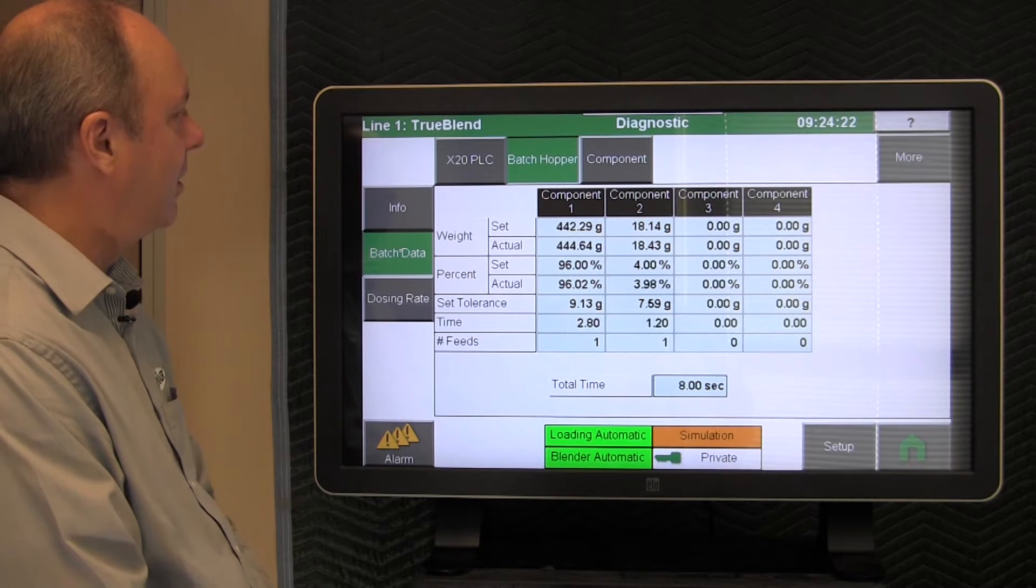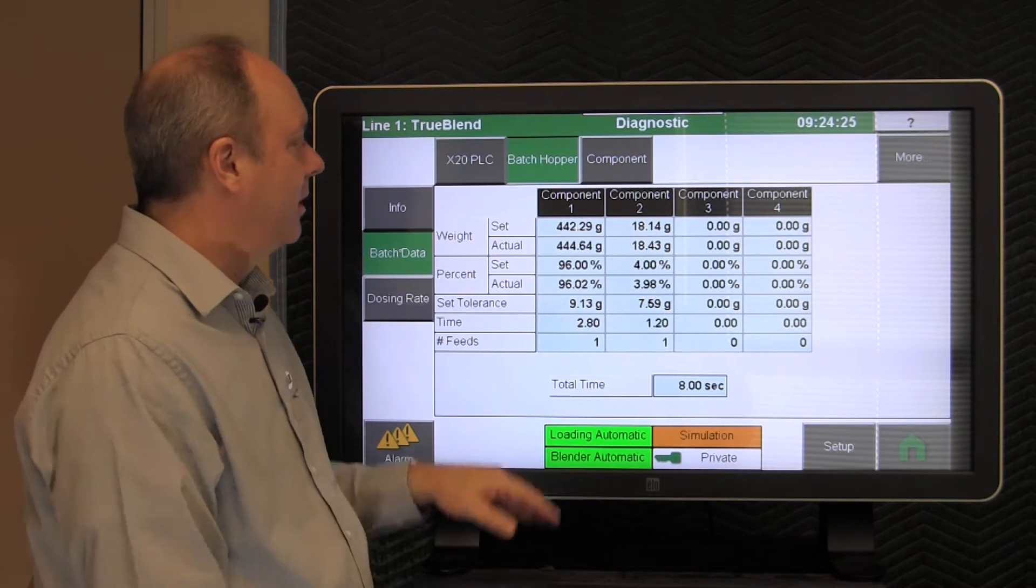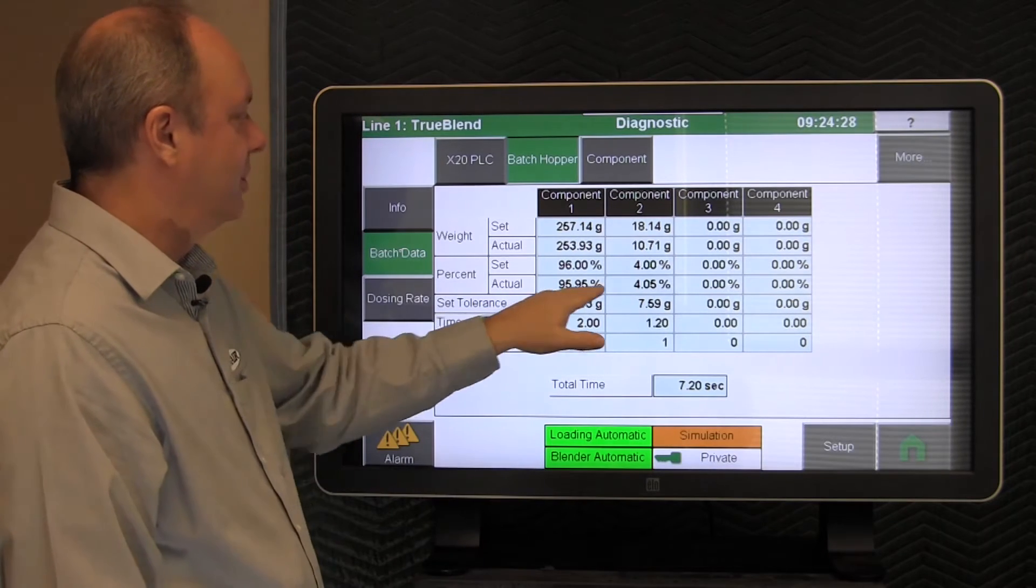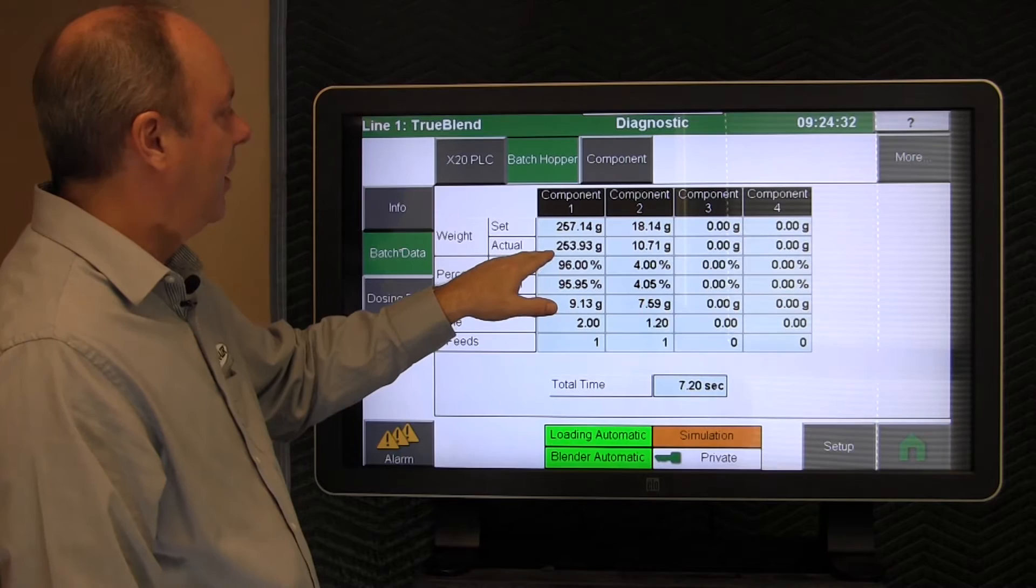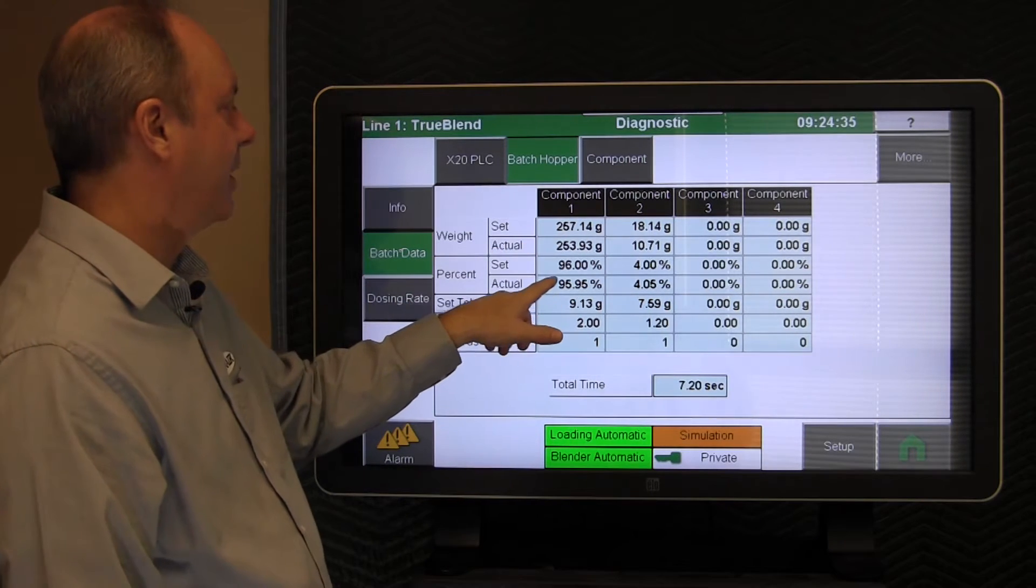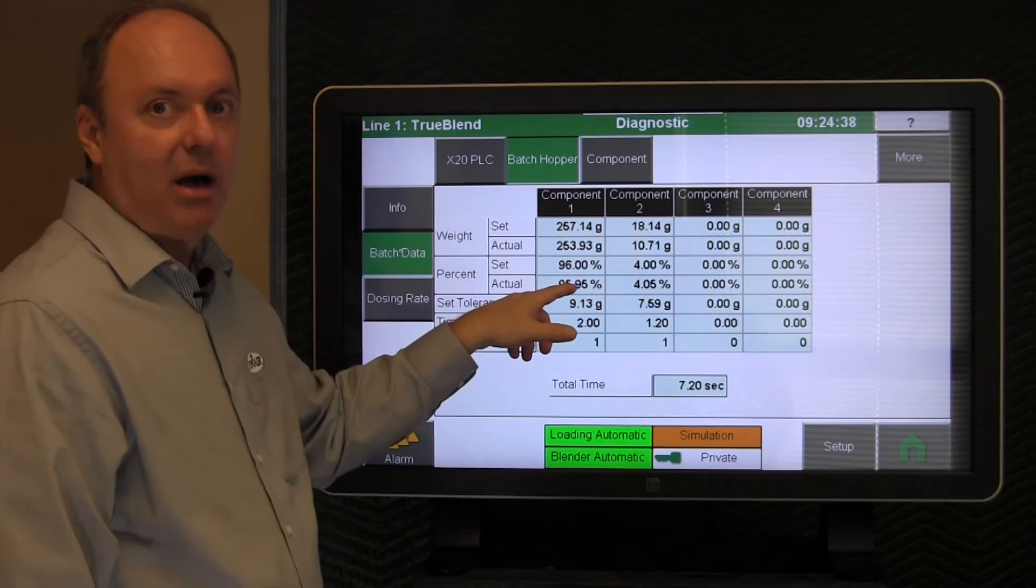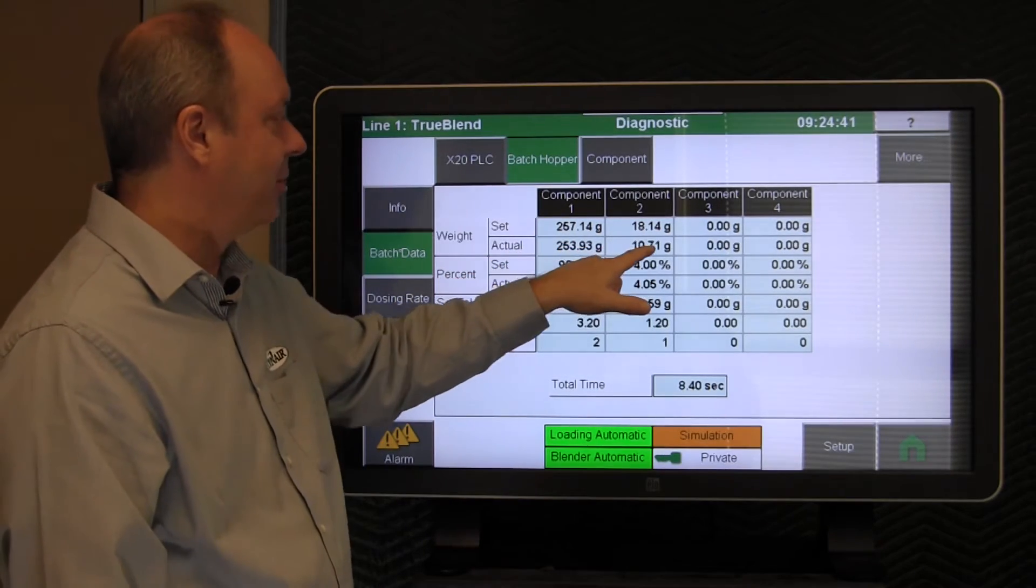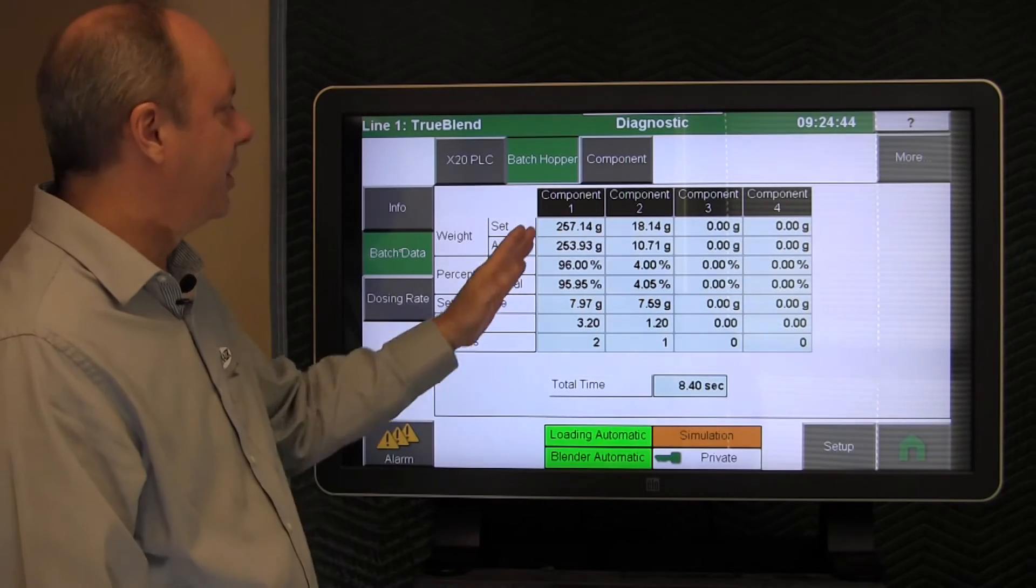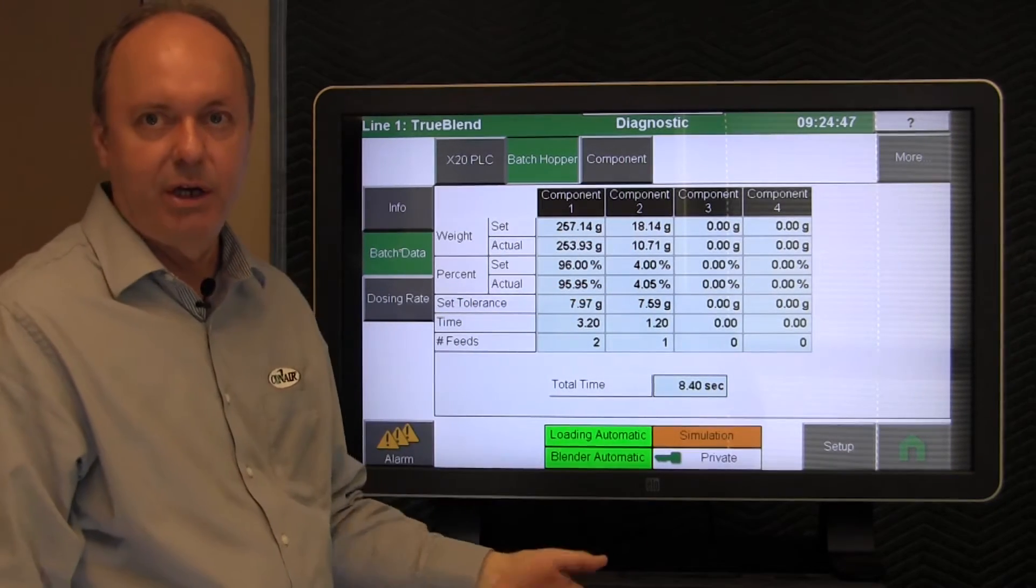For instance, if these numbers were varying wildly, the actuals, then you would be able to take a look at whether it was actually hitting its target. So in this particular case, the numbers are turning out well, but if you had a problem, the actual grams that were dosed would not be what they should be and you could tell pretty quickly which one of the components is the offending component.